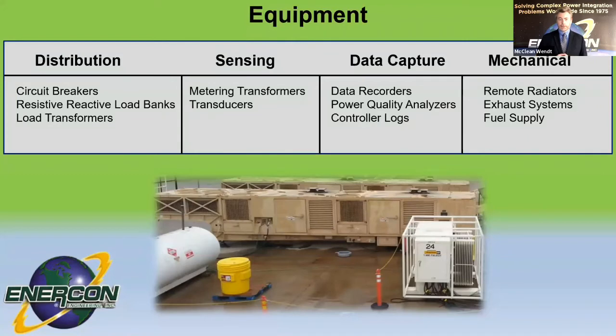Both with the load banks and the transformers, one key thing is the frequency. So if it is not a 60 hertz system, then we need to make sure that our transformers and load banks are matched to whatever that frequency is. If it's 50 or 400 hertz, or even DC. We've got a project coming up with an 800 volt DC system that we're testing. So you need to be mindful of that, and keeping your test within the ratings of your equipment.